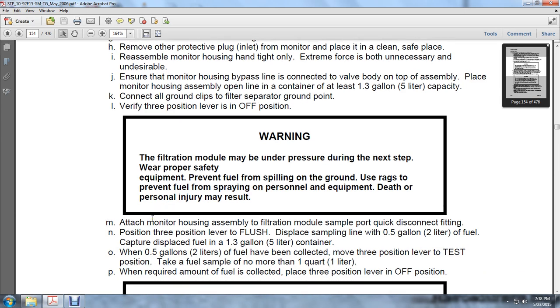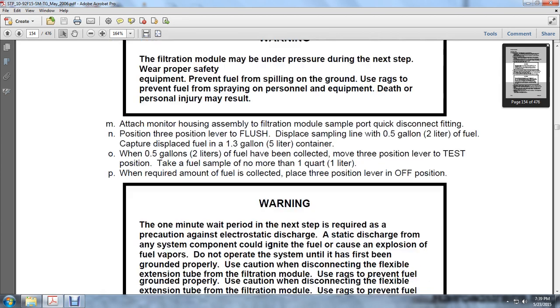Attach the monitoring housing assembly to the filtration module sample quick-disconnect port fitting. Position the 3-position lever to flush, displacing the sample line with a half gallon or 2 liters of fuel. Capture the displaced fuel in the 1.3-gallon container. When the 0.5 gallon or 2 liters of fuel has been collected, move the 3-position lever to the test position. Take a fuel sample of no more than 1 quart, 1 liter. When the required amount of fuel is collected, place the 3-position lever in the off position.